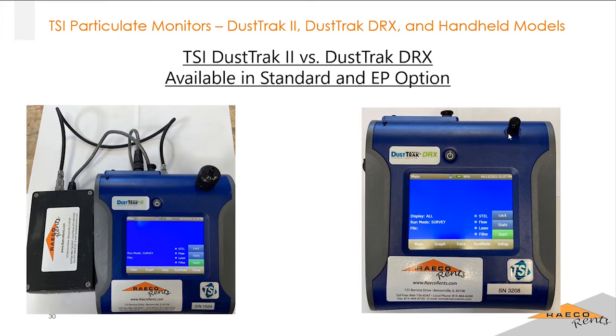And that can fail due to a number of things. It could be particulates that are stuck in the mirror. The way that the DustTrak works is basically there's a laser, and the laser's aiming at this mirror. So any dust that gets in the way of that, it's a light scattering photometer, that's what the technology is called. So, if there is any particulate in the way, or any particulates that are maybe stuck on that mirror or in the optics in front of that laser, you'll fail that zero calibration. And that's when you would know if you needed to clean things out in there.